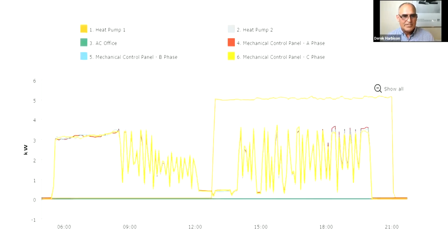So here's the first data that we got through, which is showing that first block on the left-hand side that you can see. We're talking the wriggly line at the bottom now. That first block is the air handling unit trying to adjust the air at 5:50 in the morning, and it runs and heats continuously until about 9 o'clock, where it goes into a bit of a modulating mode. That second line you can see on the right-hand side that's higher up, that's the heat pump. It only runs between, say, 12:30 and 9 o'clock at night. Just one heat pump, and this is in the depths of winter.